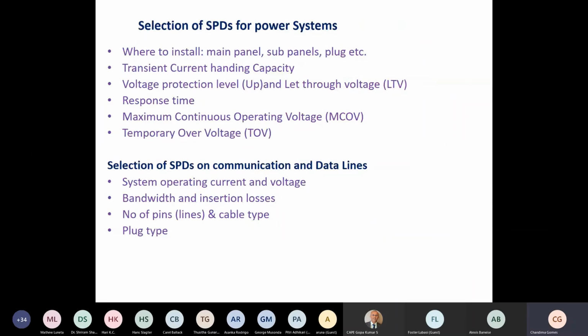So now, in order to protect your equipment, you are going to select SPDs for a power system. If you are an electrical engineer who is going to give lightning protection to a building against transients coming through the service lines, you have to consider several parameters and factors. What are they? Where to install, transient current handling capacity, voltage protection level, let-through voltage. I will explain those things later. Response time, which is not that important when you consider the UP value. Maximum continuous operating voltage and temporary overvoltage. These are the basic factors you have to consider.